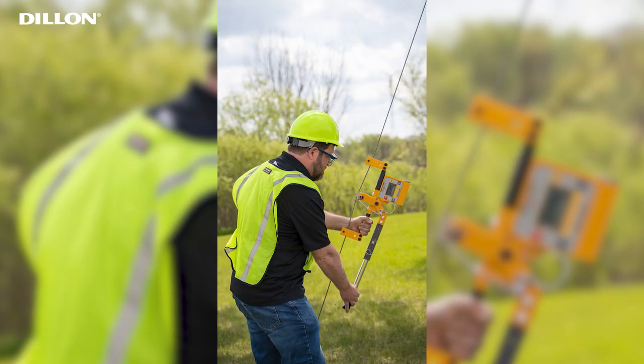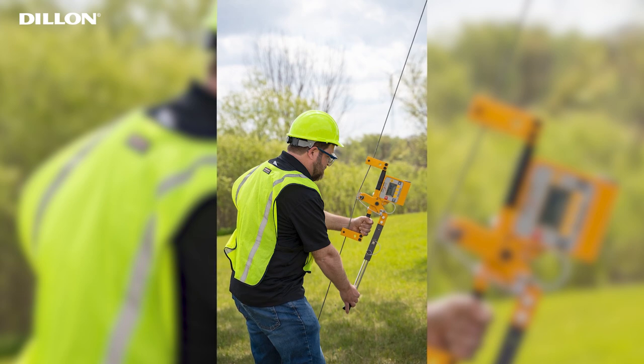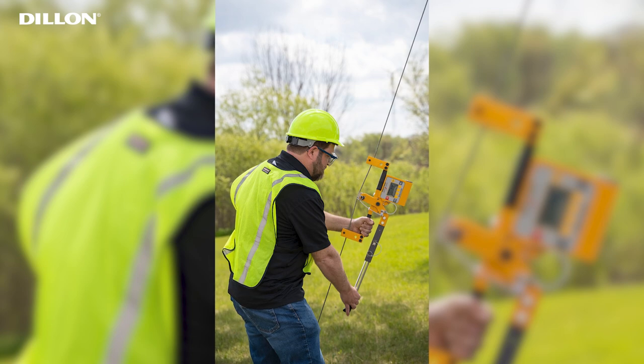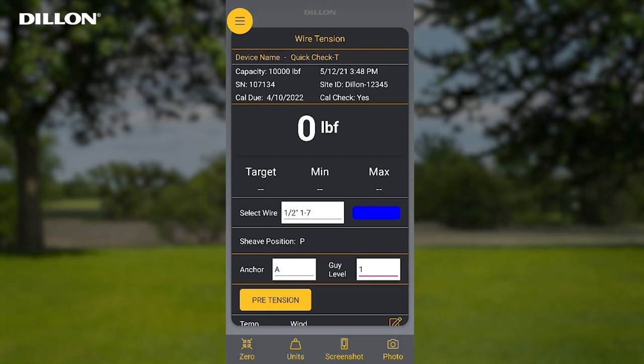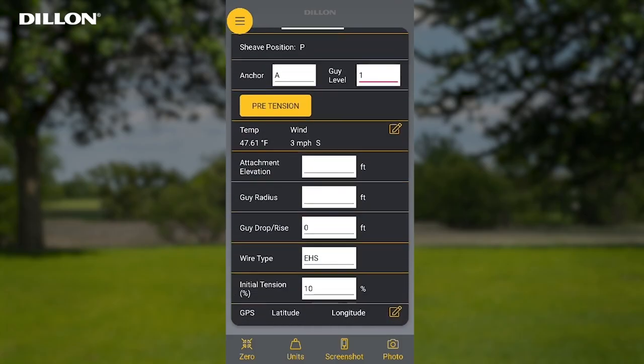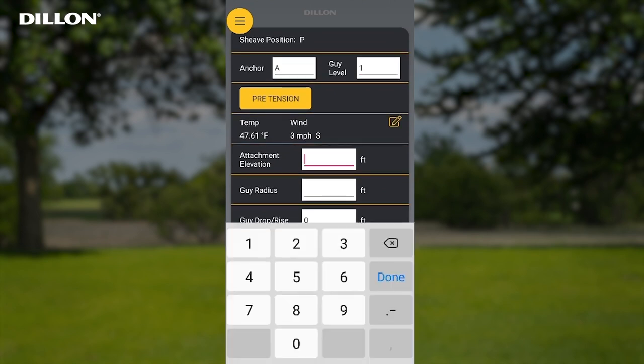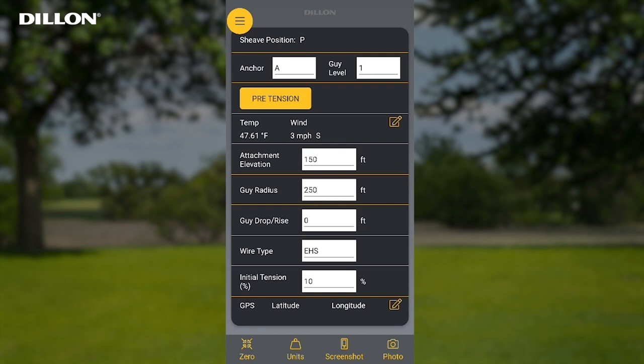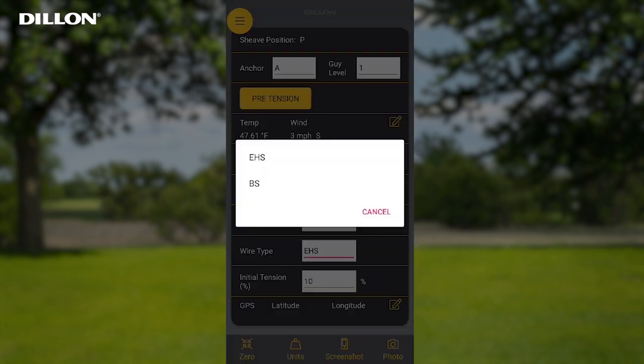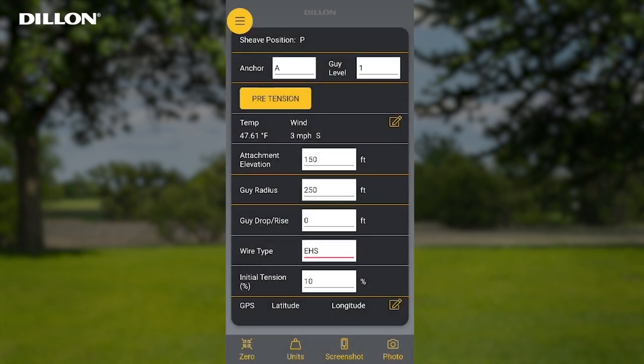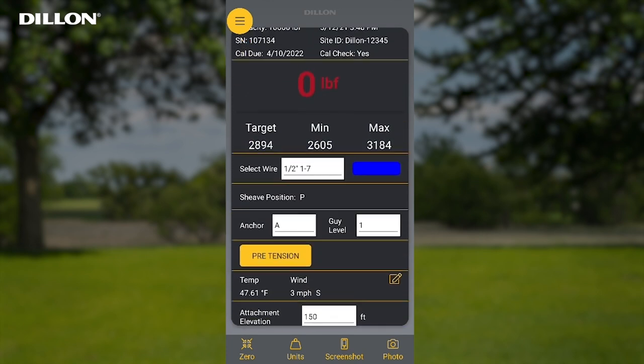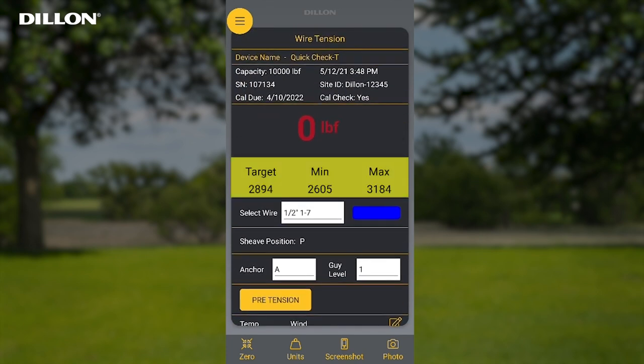Please note: it is important to have an anchor and guy level selected, as the pre-tension and post-tension readings are stored with reference to the chosen selections. The next step is to enter the tower measurements by pressing the white boxes next to the labels. At this time, you can also change the wire type from Extra High Strength (EHS) to Bridge Strand (BS) and set the initial tension percentage. Once the tower measurements are entered, the target min and max tensions are calculated and displayed under the live tension reading.